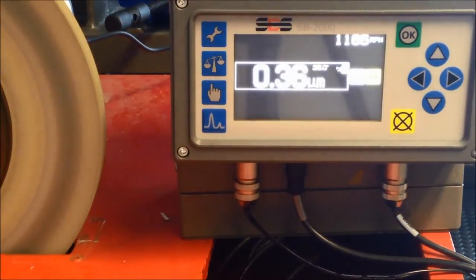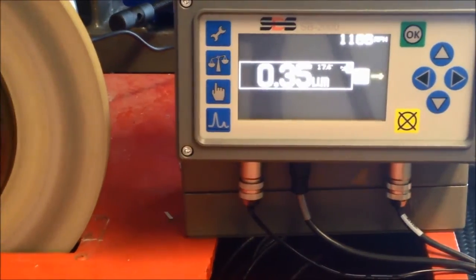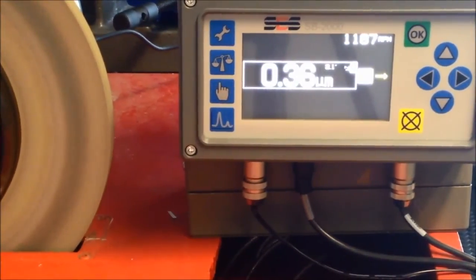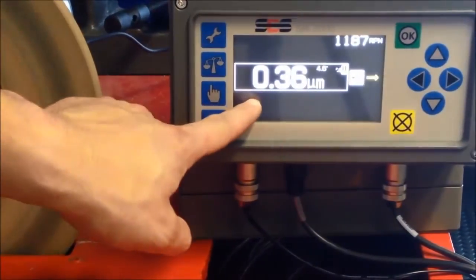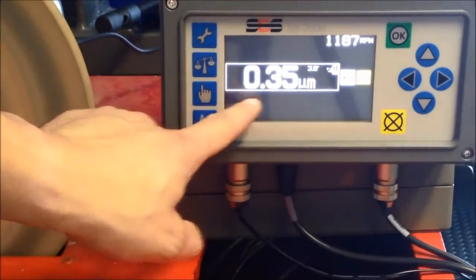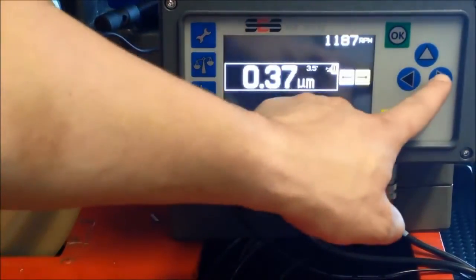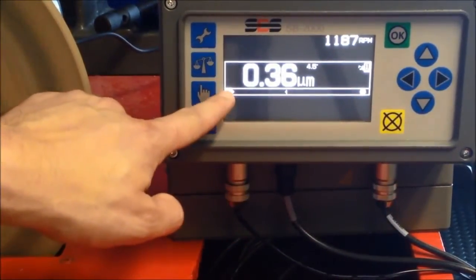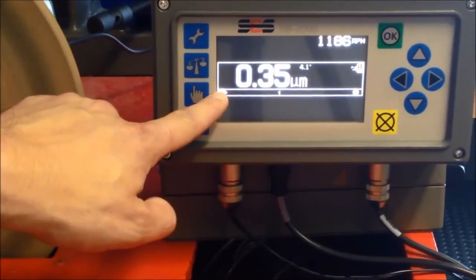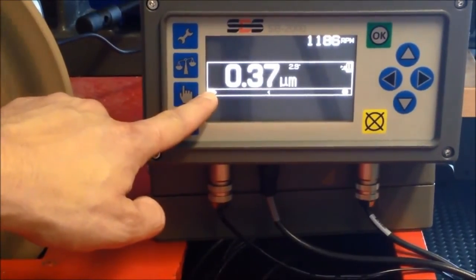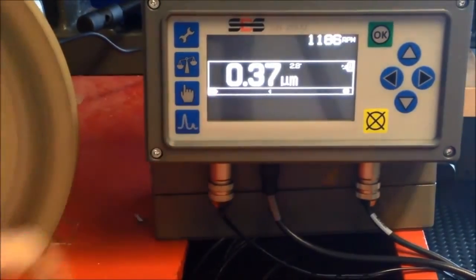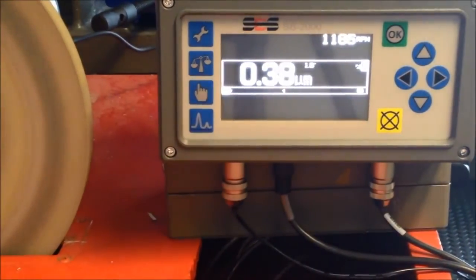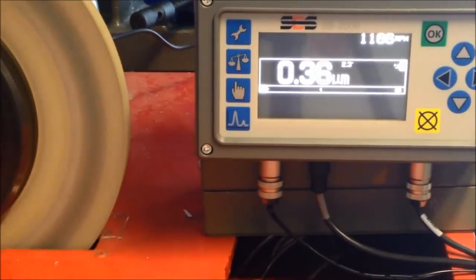We can see that the spindle vibration has been reduced to around 0.4 microns. If we recall, our initial grinding wheel unbalance was inducing a spindle vibration of 24 microns. So a 60-fold decrease has been achieved.